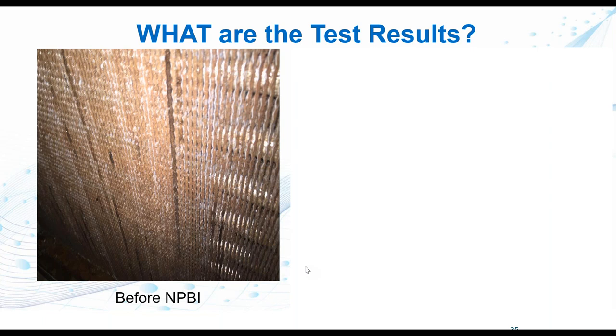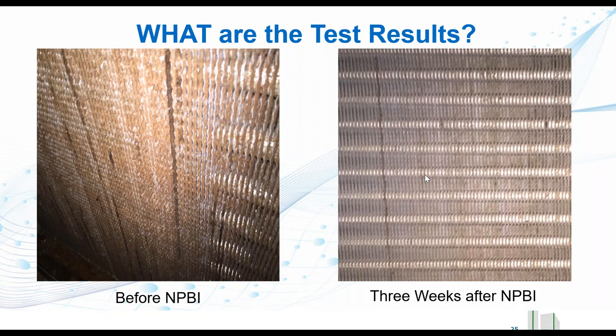While the surface of that coil looks clean, a measure of the pressure drop across the entire depth of that coil will tell a different story. But 3 weeks later on this very same coil, this is a photo. It wasn't just the surface of this coil that was clean. Pressure transducers actually showed the pressure drop through the depth of the coil to be near the original factory specs. So needlepoint bipolar ionization technology, if it's installed at the coil, it can clean the length and the depth of the coil. In addition, it's dumping ions into the space to combat whatever is present, whether it's bacteria, viruses, pathogens, mold spores, etc.